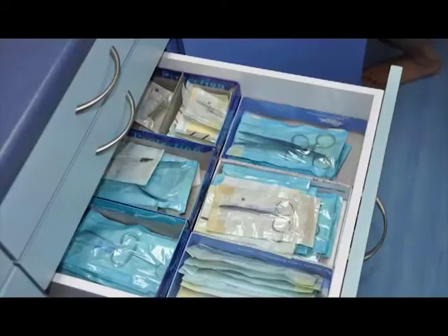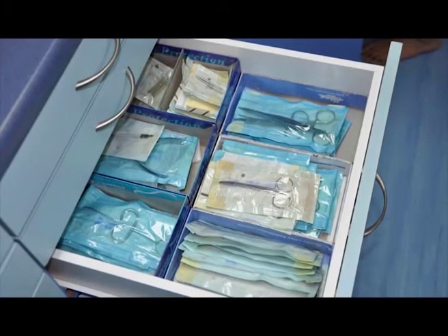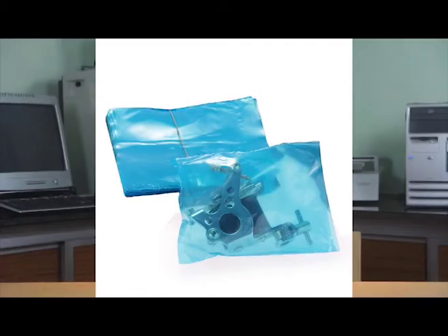The selection of packaging material. This is also one of the important characteristics. Industry is able to select the best type of packaging to suit whichever method of sterilization is to be used. For example, when irradiation is to be used, the packaging can be made completely of plastic. Similarly, when the contents are required to remain sterile for a longer period of time, the thickness of the packaging material can be increased accordingly.